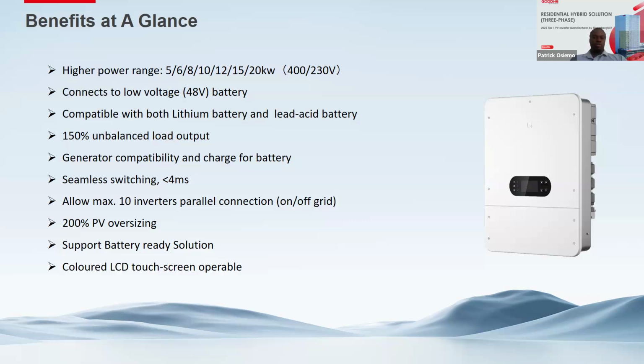So we'll be using a 48 volt battery system. I'll take you through the battery brands that are compatible with this inverter. Apart from the inverter being compatible with lithium batteries, it's also compatible with lead acid batteries. So if you have a client who's still banking on lead acid batteries before they die out, you can still install the ETLV, and then later on you can swap the lead acid batteries with the GoodWe lithium-ion batteries. Because three-phase homes are not perfectly balanced in terms of loads on each phase, the ETLV is capable of outputting 150% power, which is unbalanced.